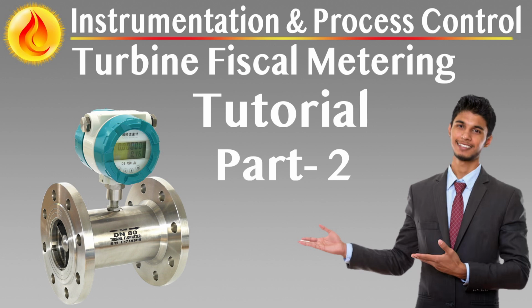Instrumentation compliance for hazardous and outdoor conditions. All field instruments intended for installation in hazardous areas must carry valid certification from a recognized testing authority. Protection methods such as intrinsic safety, explosion-proof enclosures, or increased safety designs must be compatible with the project's electrical classification zones, gas groupings, and temperature classes. Instruments must be capable of operating reliably under outdoor environmental exposure, including solar radiation, humidity extremes, and airborne contaminants.